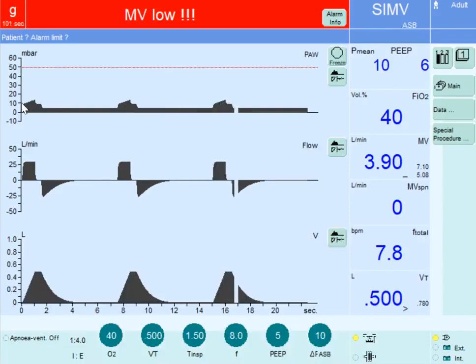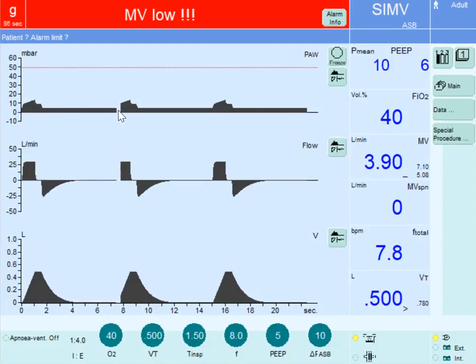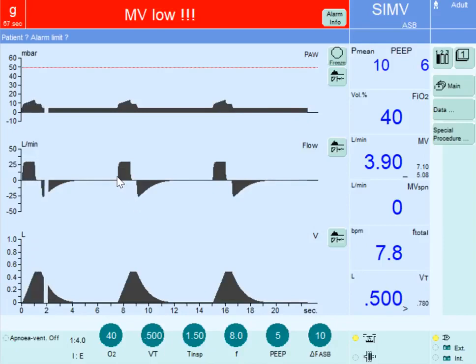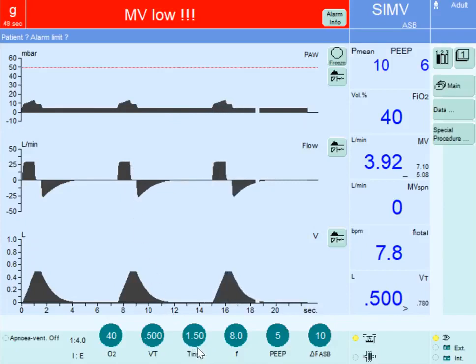If the patient is not making any efforts, they will receive intermittent mandatory ventilation of 8 breaths, each with 500 ml. The trigger for those breaths is time-based — every 7.5 seconds. Once triggered, the machine delivers a tidal volume of 500 ml with a flow rate of 30 liters per minute. The flow waveform is a square wave: a constant flow rises to 30 liters and is maintained at 30 liters. Cycling occurs after 1.5 seconds.